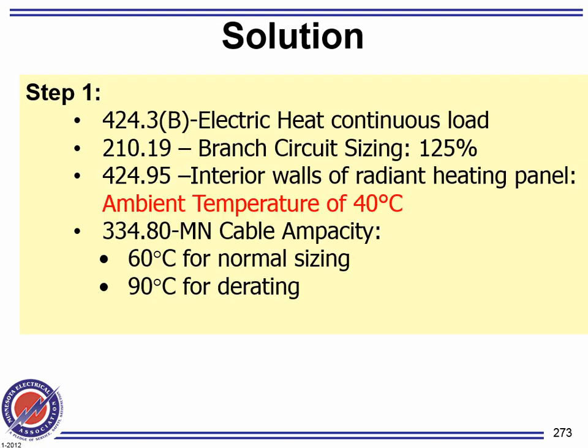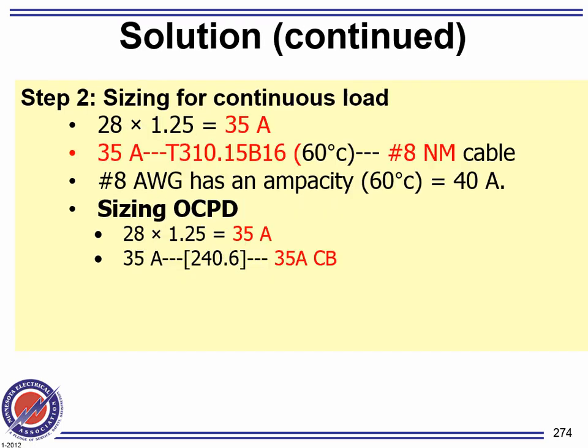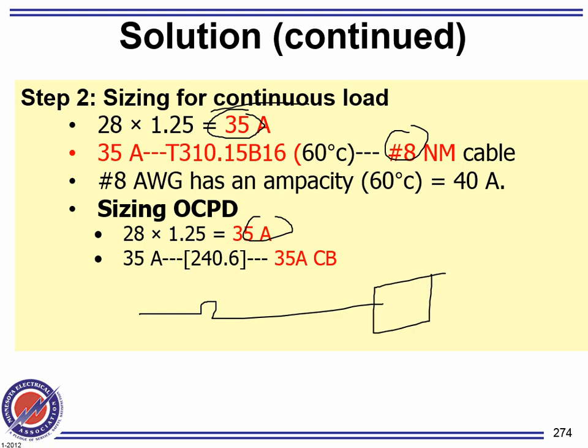Okay, so first it's continuous, then appliance circuit 125%, then I have to derate. So sizing based on its continuous load gives you 35 amps, which is number 8. So the size of the breaker is 35. Based on continuous load, you're done. You get 35 here, and your conductor gets number 8. Now that's sizing for continuous load, very easy.